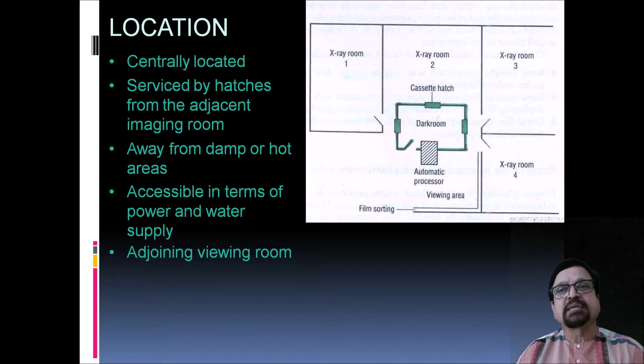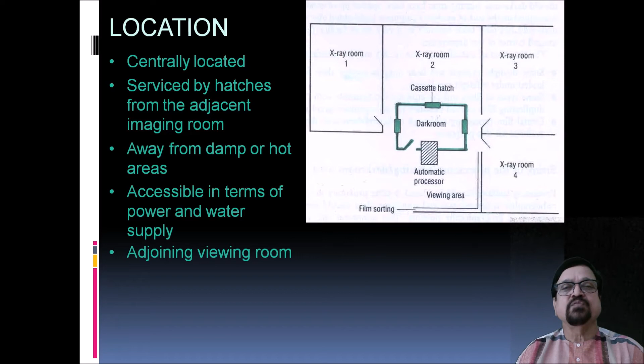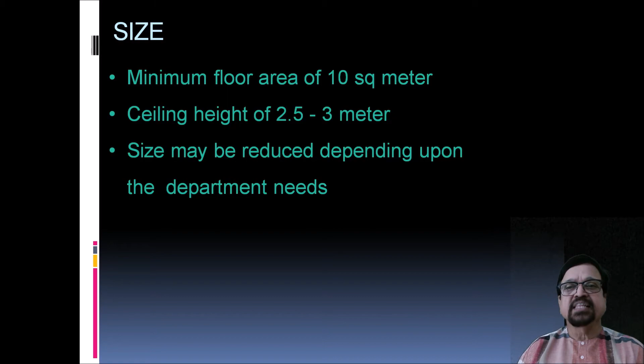It should be centrally located, served by hatches from the adjacent imaging room, away from damp or hot areas, accessible in terms of power and water supply, and adjoining viewing rooms. Now size: a minimum floor area of 10 square meters, with a ceiling height of 2.5 to 3 meters. Size may be reduced depending upon the departmental need.